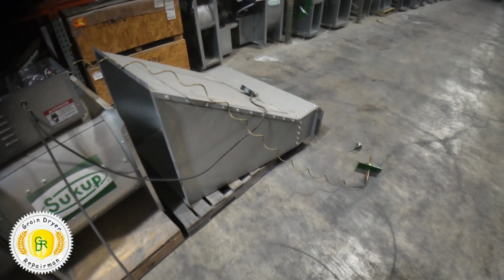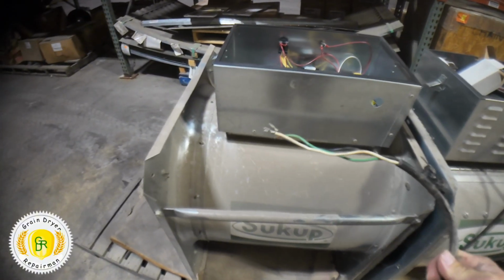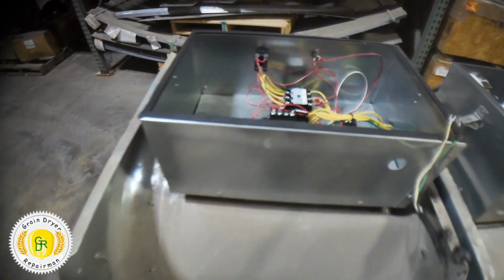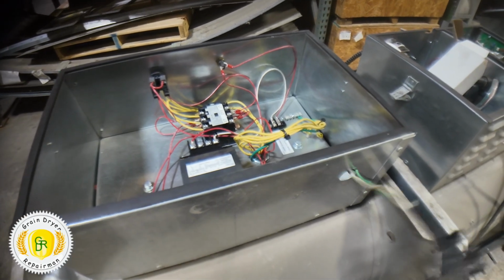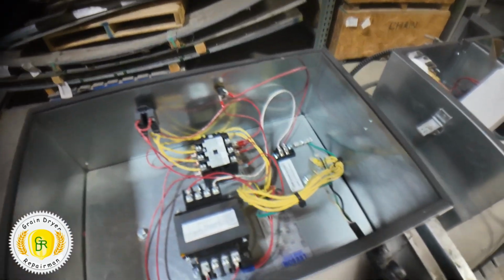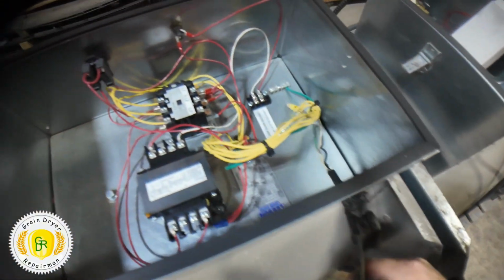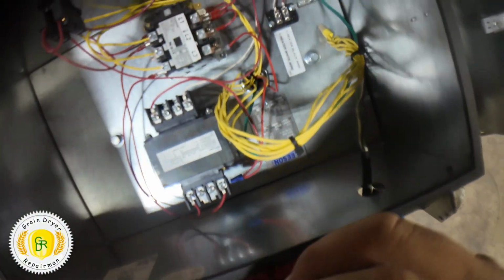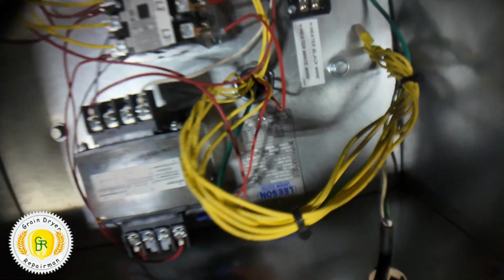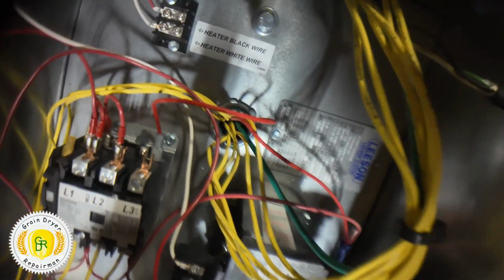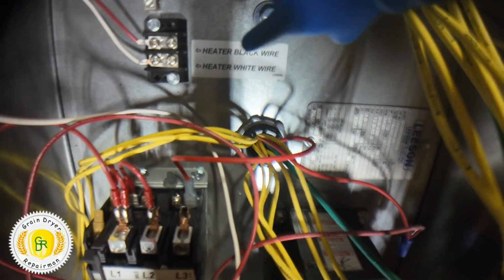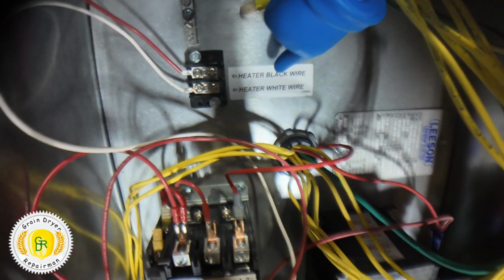Up here, we have 2 cords that come out this side of the burner. One is the transition high limit. The other is the burner cord, the power cord. We go in the side of the burner, the fan, take this cord from the burner to the fan. In the fan box, you're gonna see heater black wire, heater black wire, heater white wire.